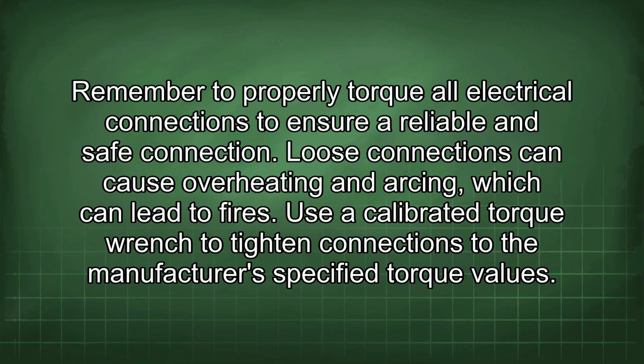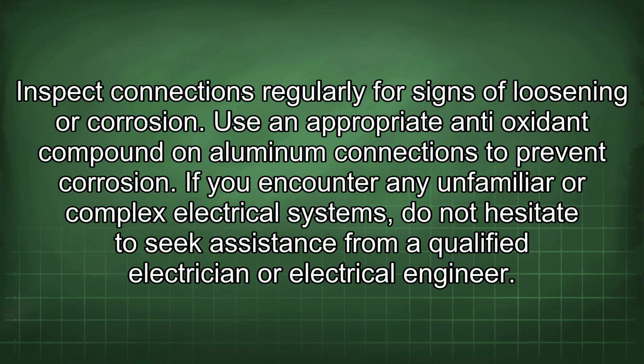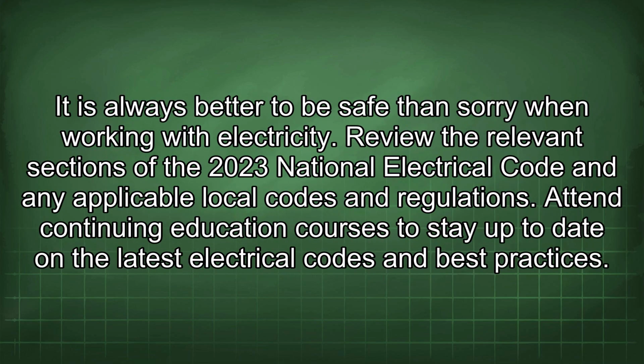Loose connections can cause overheating and arcing, which can lead to fires. Use a calibrated torque wrench to tighten connections to the manufacturer's specified torque values. Inspect connections regularly for signs of loosening or corrosion. Use an appropriate antioxidant compound on aluminum connections to prevent corrosion. If you encounter any unfamiliar or complex electrical systems, do not hesitate to seek assistance from a qualified electrician or electrical engineer. It is always better to be safe than sorry when working with electricity.